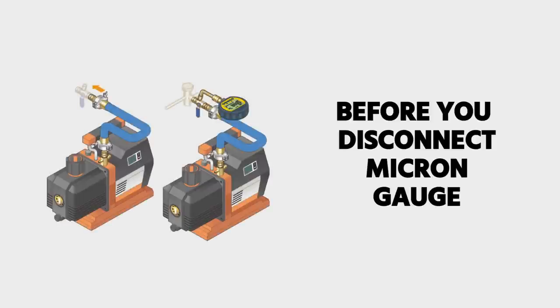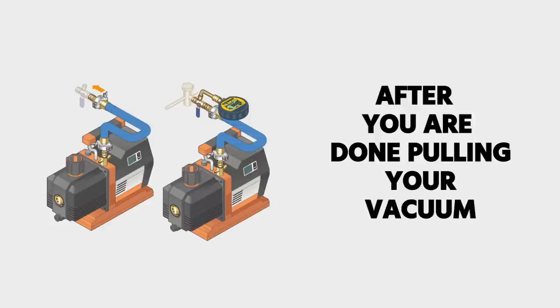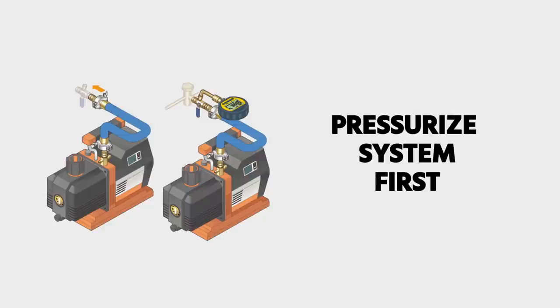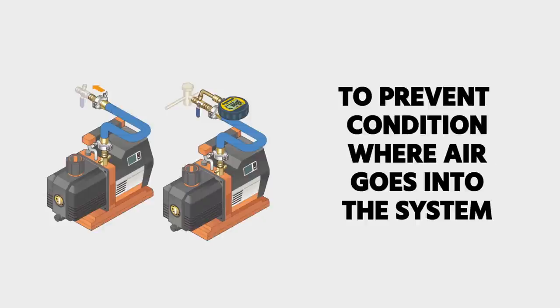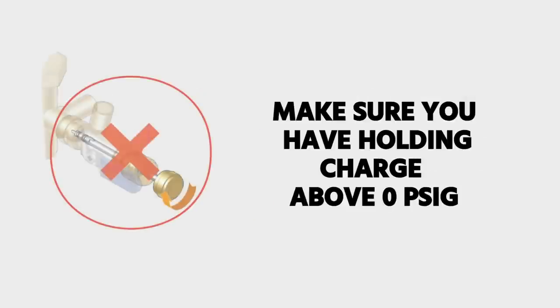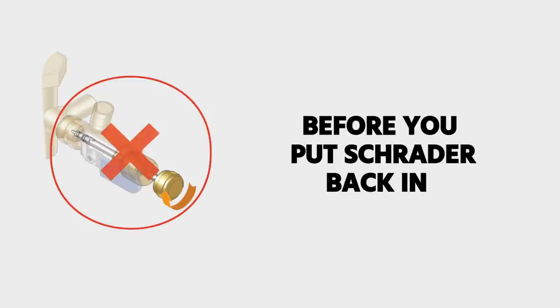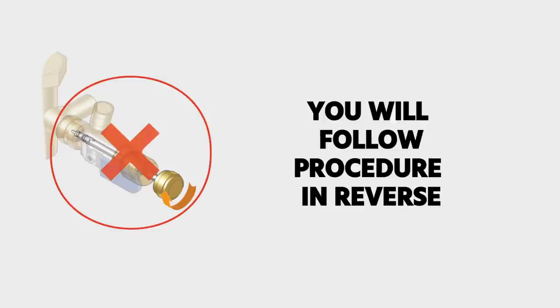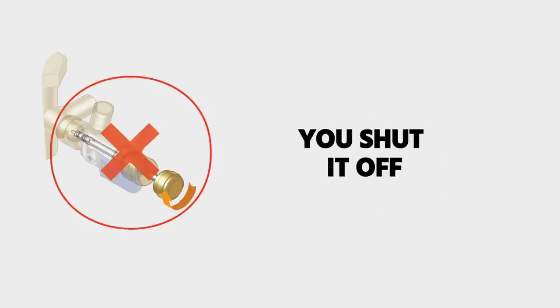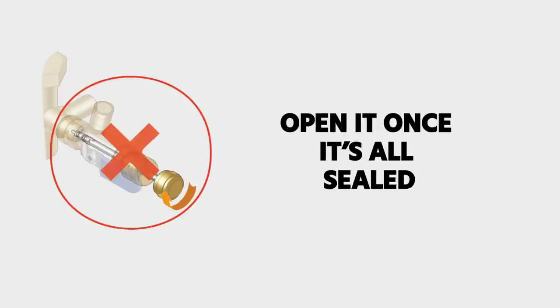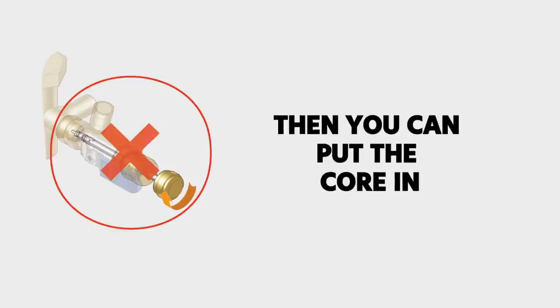Before you disconnect the micron gauge or change anything after you're done pulling your vacuum, you want to make sure to pressurize the system first. That way you are not going to have a condition where air goes into the system. You want to make sure that you have a holding charge above zero PSIG before you go ahead and put that Schrader back in. And of course, it's safe to do because you're going to follow that procedure in reverse, where you shut it off, you put the Schrader in, and then you open it once it's all sealed, and then you can put the core in.